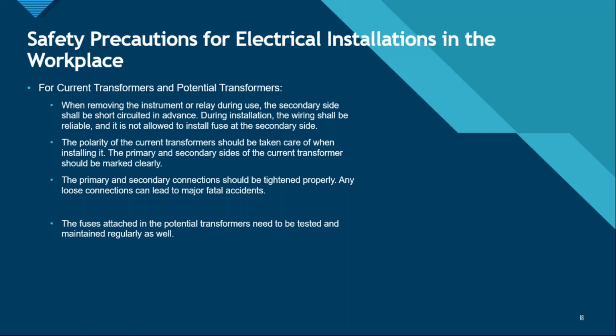The polarity of the current transformer should be taken care of. They should be marked clearly, not to be confused from the primary winding to the secondary winding. The primary and secondary sides of the current transformer should be marked clearly. The primary and secondary connections should be tightened properly. Any loose connections can also lead to major fatal accidents or arc blasts.